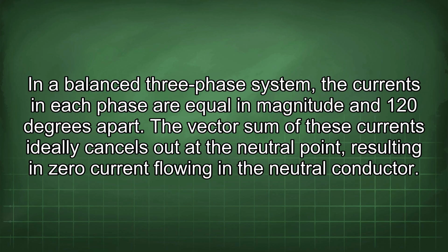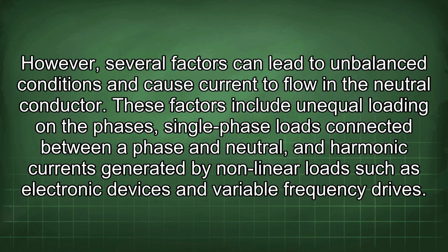In a balanced three-phase system, the currents in each phase are equal in magnitude and 120 degrees apart. The vector sum of these currents ideally cancels out at the neutral point, resulting in zero current flowing in the neutral conductor. However, several factors can lead to imbalanced conditions and cause current to flow in the neutral conductor. These factors include unequal loading on the phases, single-phase loads connected between a phase and neutral, and harmonic currents generated by nonlinear loads such as electronic devices and variable frequency drives.